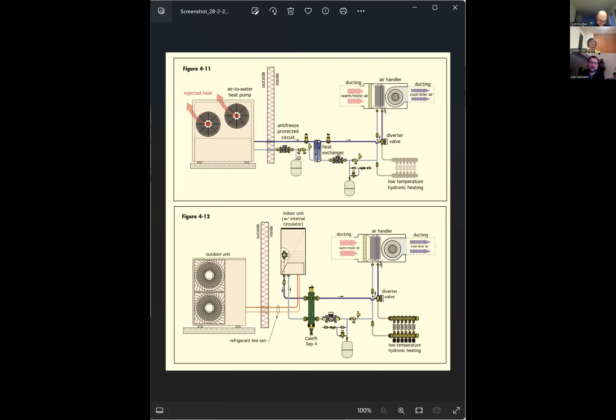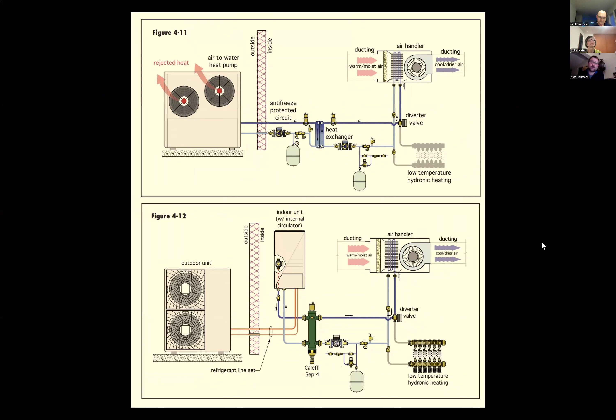So I can share the screen of the air to water heat pump systems. Generally, there are two types of air to waters. One is a monoblock system, which is up here. That means all the refrigerant is outside of the building, and there's no refrigerant inside. As the refrigerant is changing more towards propane-based, it becomes more flammable. So newer refrigerant blends are eventually going to have requirements where you can't vent them in the house, and you can't have any leaks. So the monoblock system, which is also a Stiebel Eltron, what I'm using, is a better option because it's safer to have in the house.